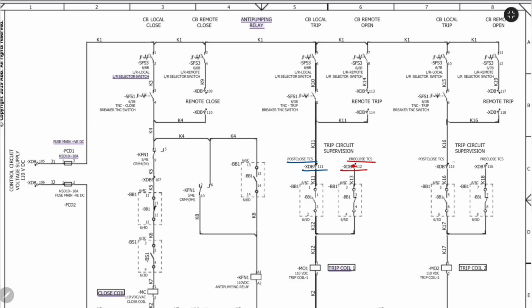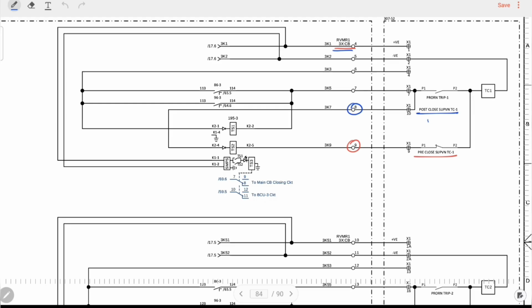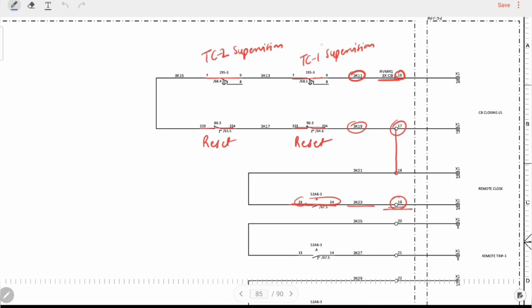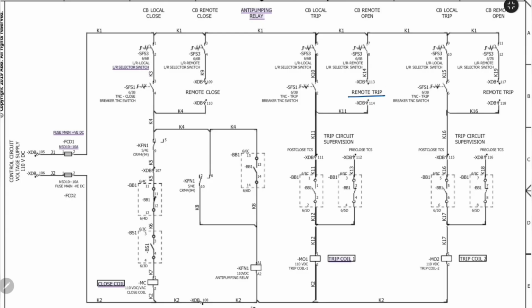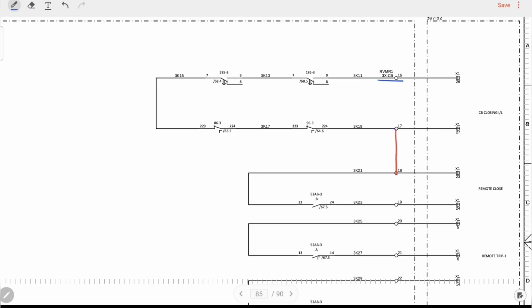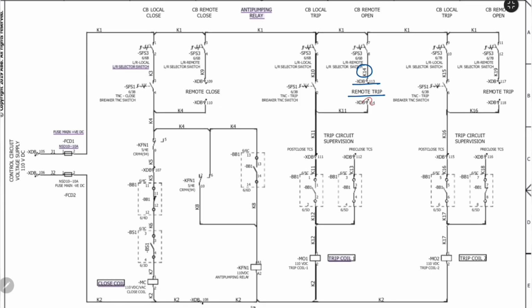If your breaker uses dual trip coils, repeat the same wiring for trip circuit number 2 using the corresponding spare terminals. With the supervision loop completed, the panel now recognizes a healthy trip circuit and permits remote operation. For remote tripping using the panel TNC switch, connect breaker terminal XDB113, K14 to Siemens terminal 3xCB20, 3K25. Then connect Siemens terminal 3xCB21, 3K27 to breaker terminal XDB114, K11. The panel can now trip the breaker remotely.